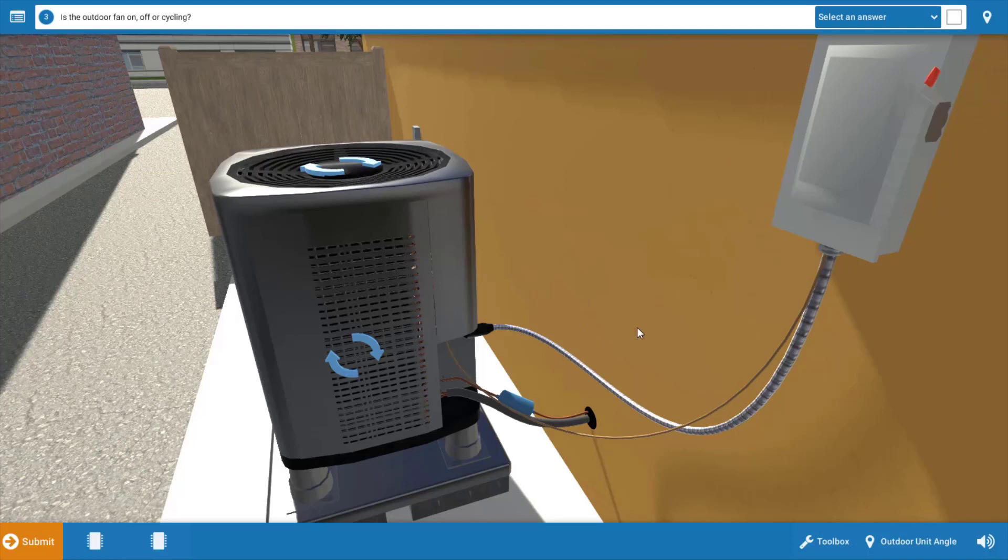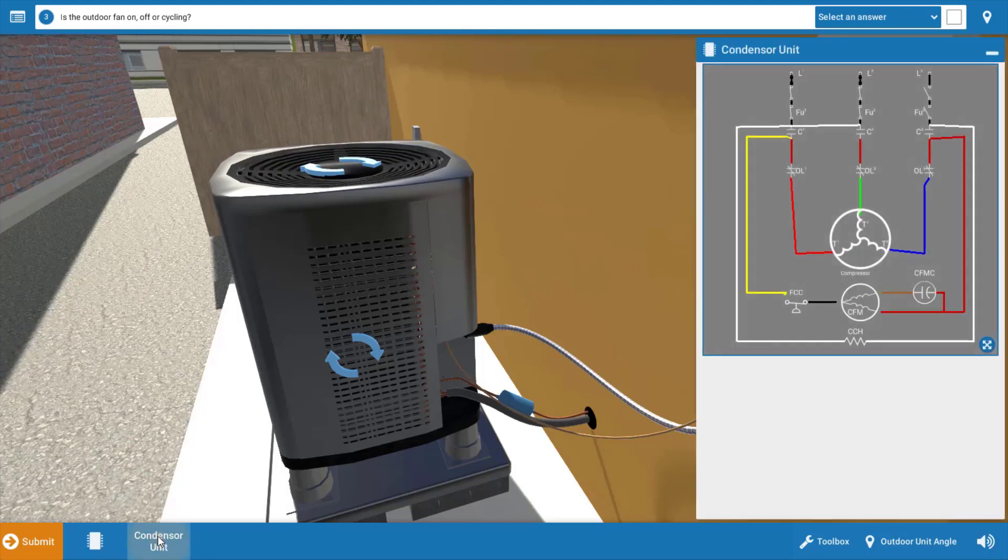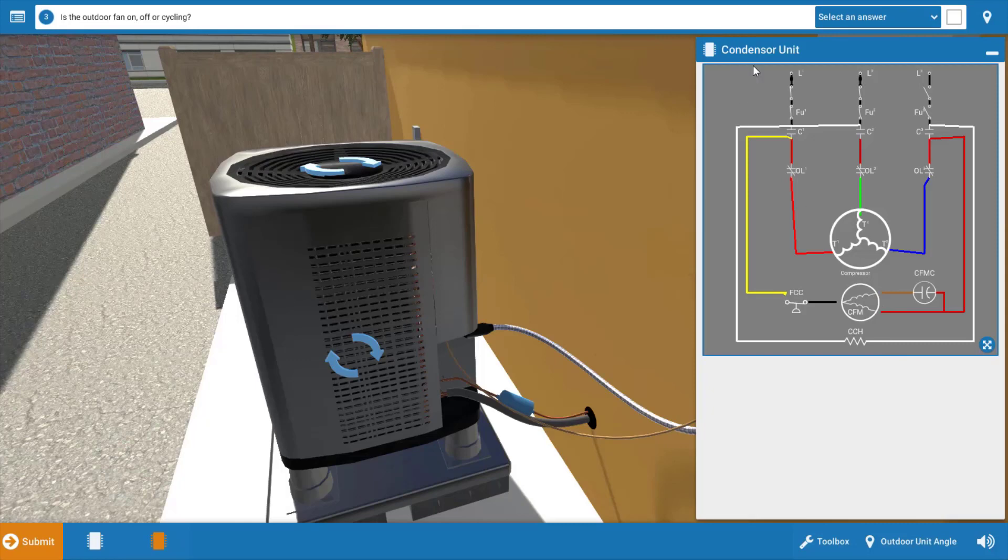Now before we go any further, let's take a look at the outdoor unit wiring diagram and come up with a list of possible causes of the malfunction here. Well, if you look on this diagram, there's actually nothing other than the main power coming in outside that's common to both the compressor and the condenser fan motor. So it's possible that we have no power coming to the outdoor disconnect.